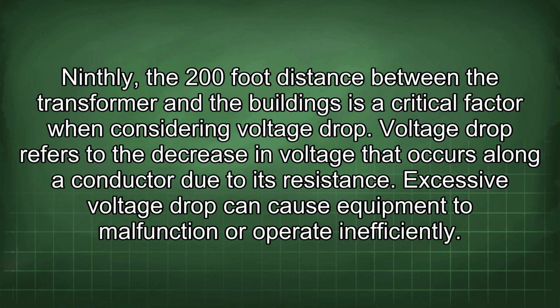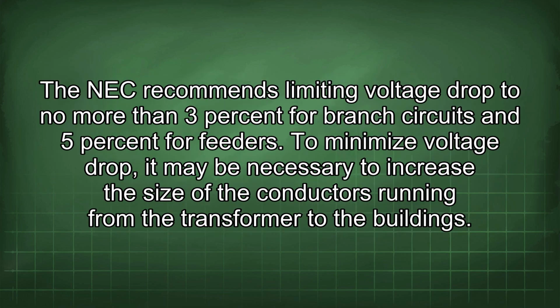Ninthly, the 200-foot distance between the transformer and the buildings is a critical factor when considering voltage drop. Voltage drop refers to the decrease in voltage that occurs along a conductor due to its resistance. Excessive voltage drop can cause equipment to malfunction or operate inefficiently. The NEC recommends limiting voltage drop to no more than 3% for branch circuits and 5% for feeders.